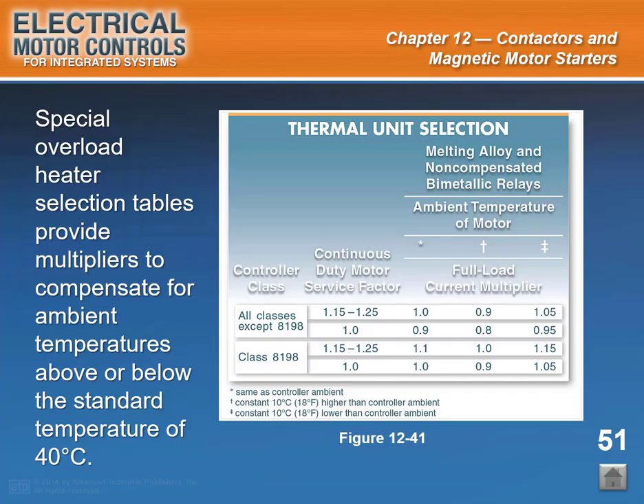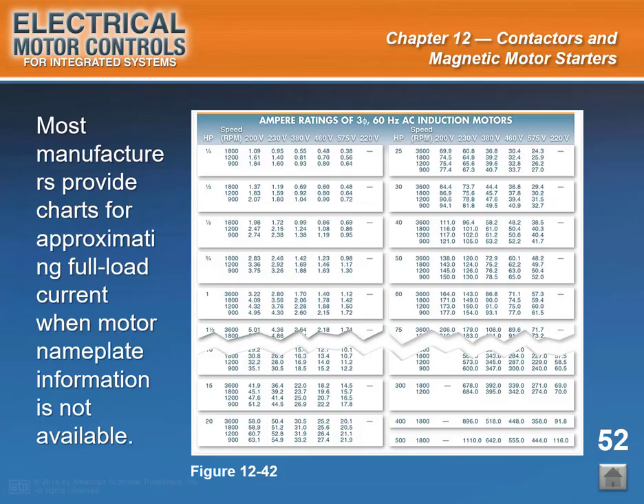Start of slide 52. Slide caption: most manufacturers provide charts for approximating full load current when motor nameplate information is not available. See figure 12-42. In rare instances, such as older installations or severely damaged equipment, it may be impossible to determine a motor full load current from its nameplate. Charts listing approximate full load currents based on average motor full load currents are available from most manufacturers when nameplates do not provide this information. End of slide 52.